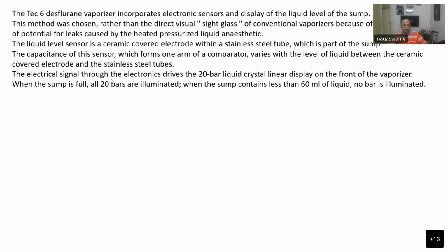So the electrical signal goes through the electronic devices, and there is a 20 bar liquid crystal linear display on the front of the vaporizer. When the sump is full, all the 20 bars will be illuminated, and when the sump contains less than 60 ml, no bar is illuminated. Because as I told earlier, that 60 ml or 50 ml is the reserve volume that will be in the sump. So the level of the liquid is seen more through the bar display rather than the visual fluid level that you see in the other sumps.